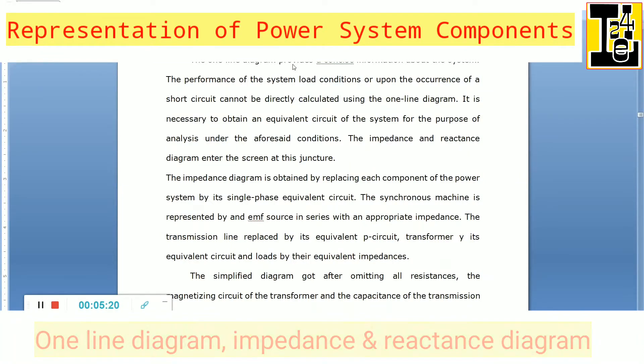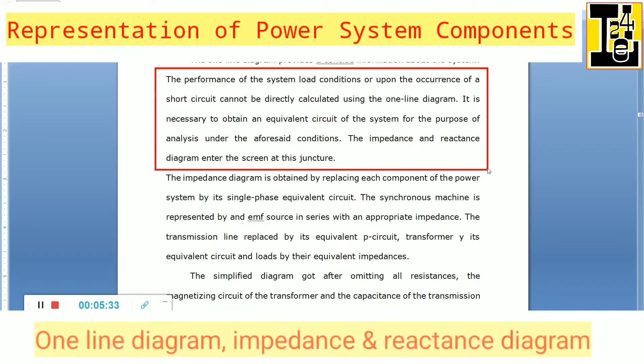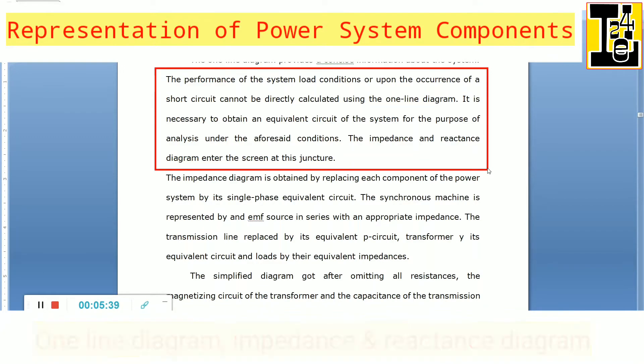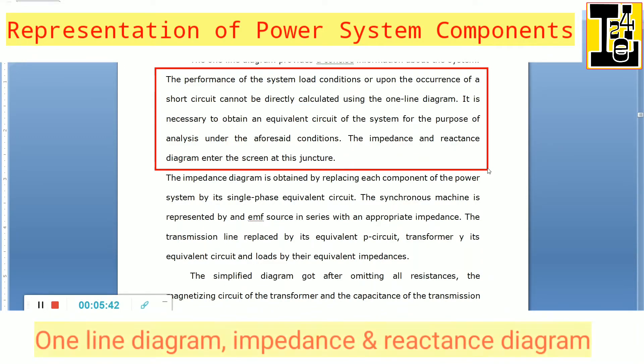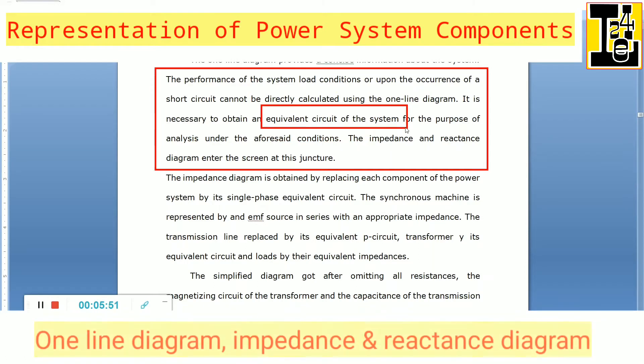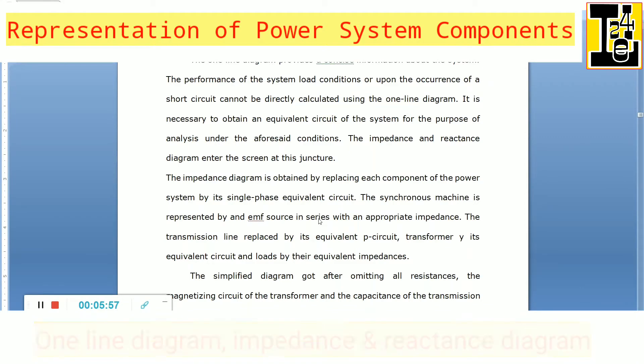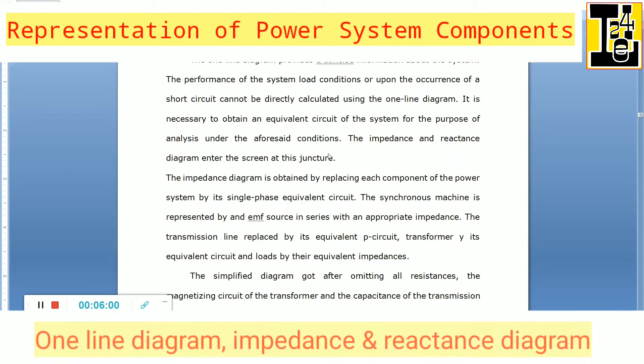The one line diagram provides concise information about the system, but performance under load conditions or upon the occurrence of a short circuit cannot be directly calculated using it. It is therefore necessary to obtain an equivalent circuit of the system for analysis under fault conditions, short circuits, or open circuits. This is where the impedance and reactance diagrams come into the picture.